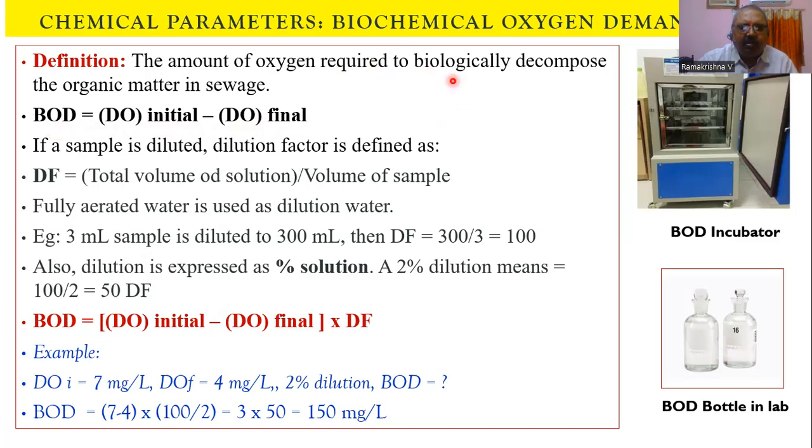When we do this test, we should keep the sample under standard temperatures for a specific period of time. These standard temperatures are called incubation temperatures. For that, we use an incubator, the BOD incubator. This is a BOD incubator where we can fix the temperature of the contents using a control device. The standard followed here is 20 centigrade for 5 days. So we have to keep a sample in this at 20 centigrade for 5 days.